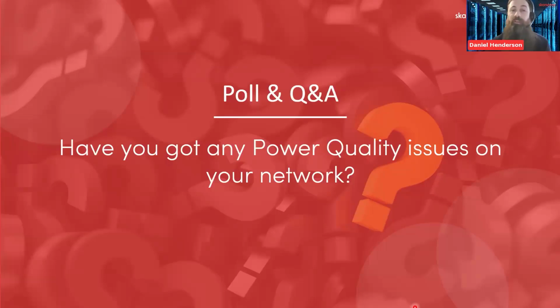And I ask because again, in a previous facility that I was the engineering manager of, looking at this, they had, I don't know, 10 production lines approximately, each operating in their own silo of production. And when asked individually, have you got any power quality issues? No, nothing really. Then when you start looking at it, you see they're on the under voltage side, on the low level, and then you start looking at when they've had issues: we have an under voltage trip maybe every 2 weeks, but it's only off for an hour or 2 hours, something like that. But you're talking $10,000 per hour worth of production, and every production line had the same. So again, every 2 weeks, you're talking around sort of $100,000 to $200,000 of lost production, plus the impact and the downtime. So again it's just a question, just to see what that looks like.